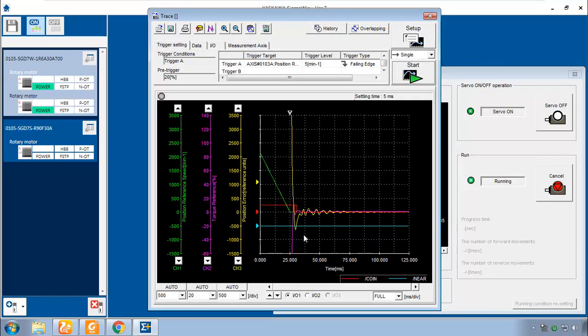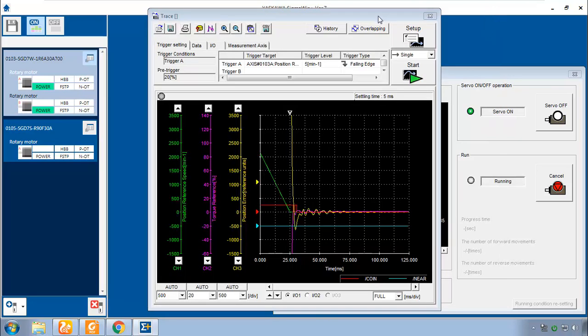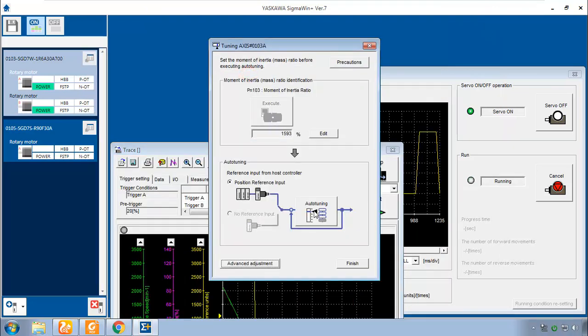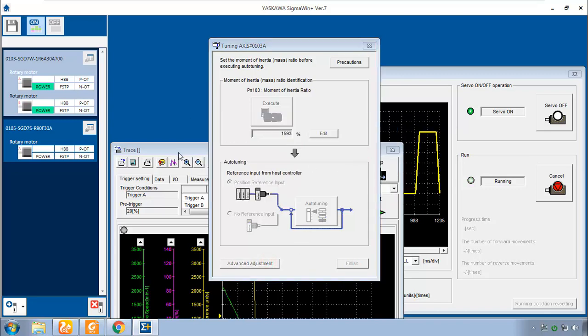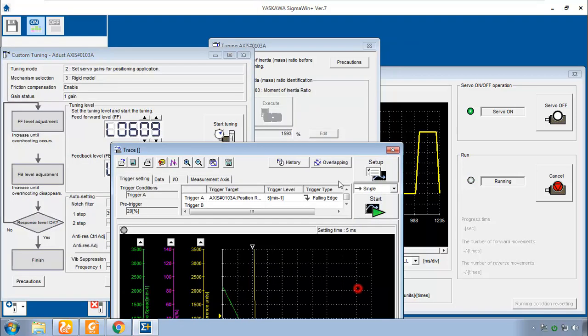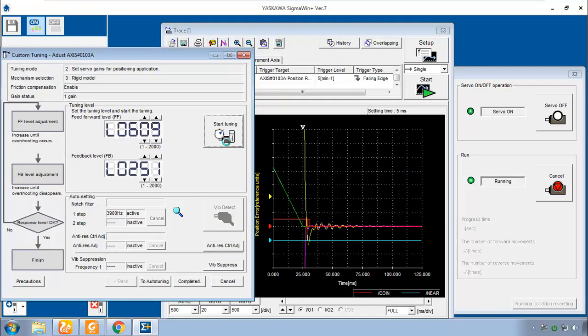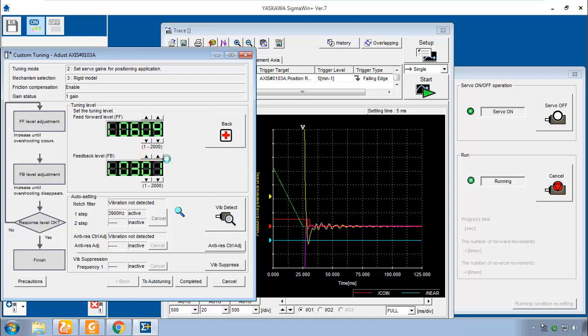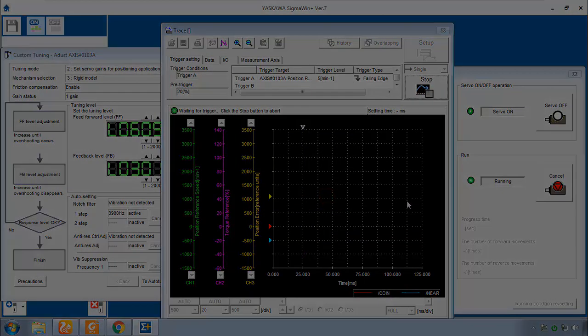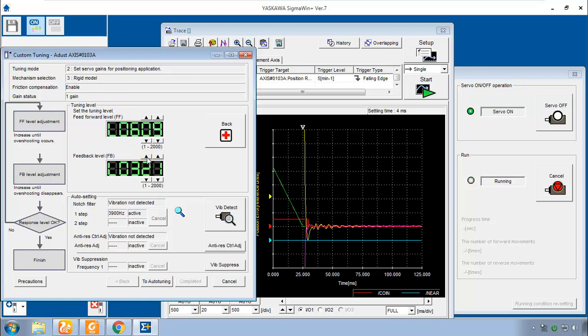Go back up, looks like it started to get better. 36 is too low, 37, alright, might do 38, 39. Might be some trial and error and you may have to come back to this later on if you want to increase the Feedback level even more. So I'll leave it here for this machine at 3900. Now let's see if this helped our settling time at all. Still dipped down a little bit too far didn't it. Let's go back to custom tuning. If it's grayed out that means there's already a window open here somewhere. Yes, okay. So let's go to Advanced Adjustment, Custom Tuning, go through all this again. Move this over and we'll do start tuning again.